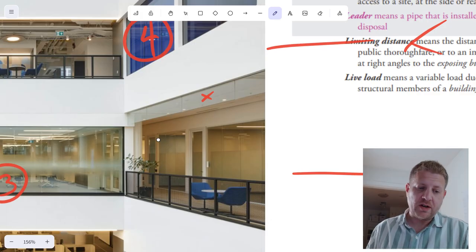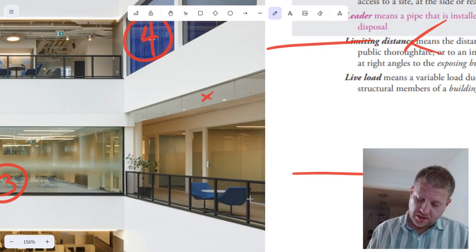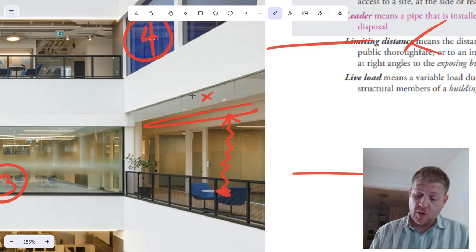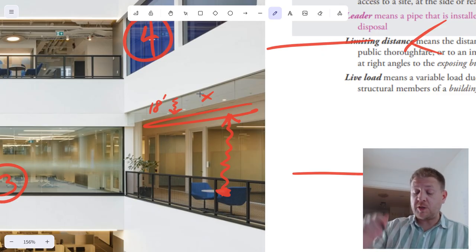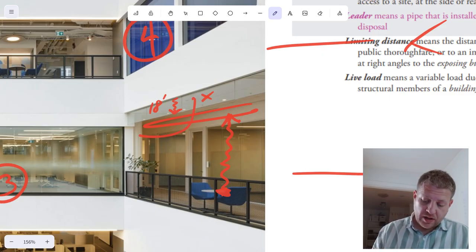But if you have a fire on this level, level 3, say it starts right here on this desk, someone sets the chair on fire, I don't know, and it's burning, the smoke's traveling up, right? And it can't get out of this floor area until it builds up enough smoke that it comes down. That's probably like 18 inches, something like that. It basically has to fill up that ceiling space before it can travel underneath and move up.